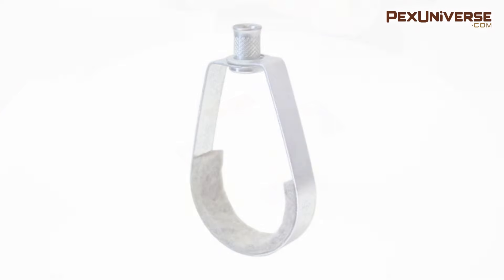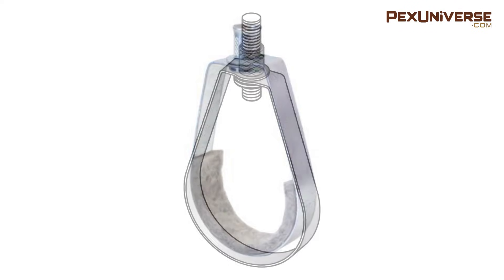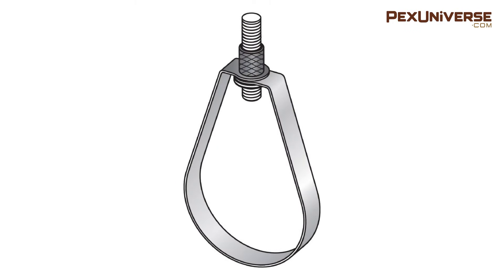The adjustable swivel ring hanger is designed for the suspension of non-insulated stationary pipelines. The knurled insert nut allows vertical adjustment after installation. You can get these from 1/2 inch pipe all the way up to 8 inches which can hold around 300 to a thousand pounds respectively.